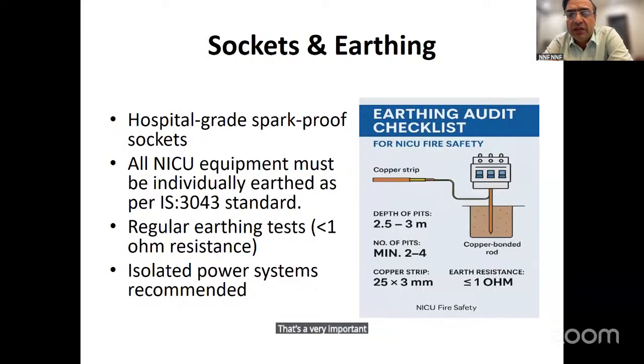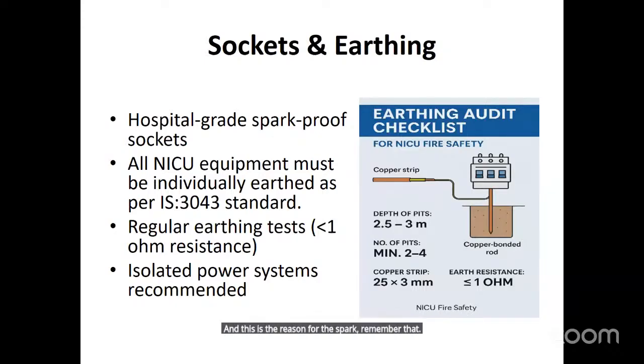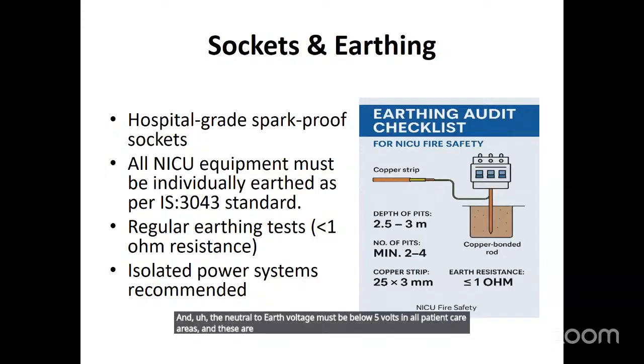We have to remember that no extensions, no damaged wires, and this is the reason for the spark. Remember that. Yes, sir. So, coming on to the earthing point, all the NICU equipment must be individually earthed as per the Indian standards, and the neutral to earth voltage must be below 5 volts in all patient care areas. And these are the certain points which are labeled here: earthing audit checklist.